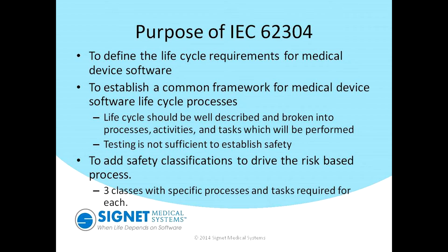I've heard people say: CE mark is easy to get in Europe, let's get a CE mark and worry about this later when we've made revenue. Well, in 2015 — and I may have a mistake on this because I learned something new at this conference — ISO 13485 has one little line in it that says for your software development process you need to be 62304 compliant. So a lot of people relying on a CE mark for their software-enabled medical devices are going to be in difficulty as that phases in.